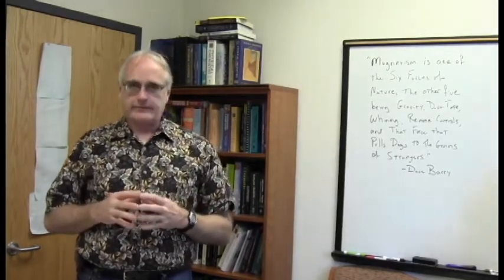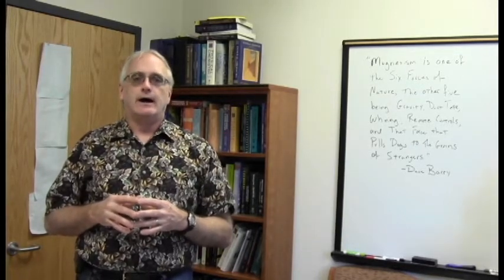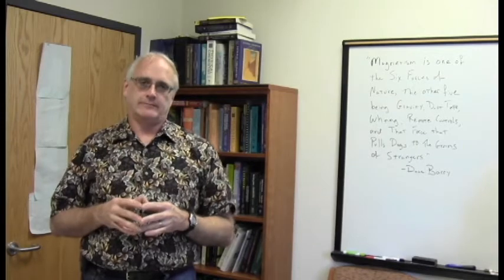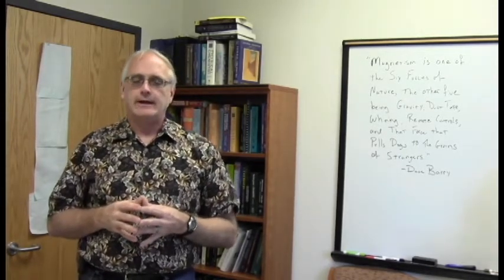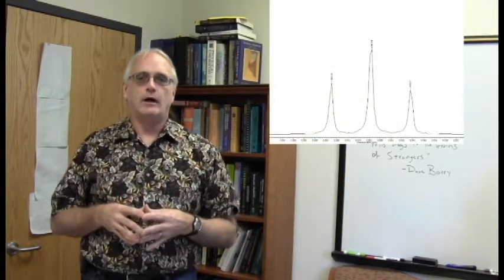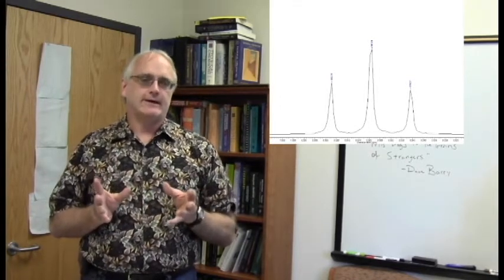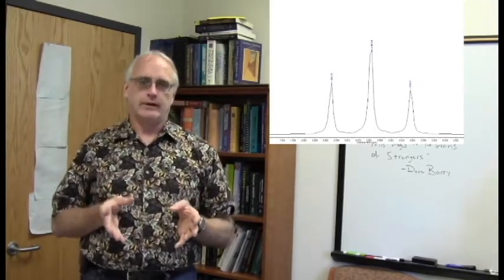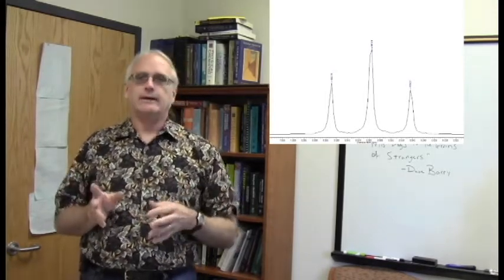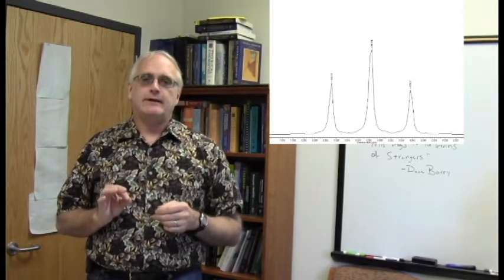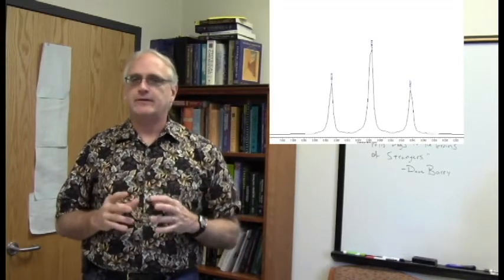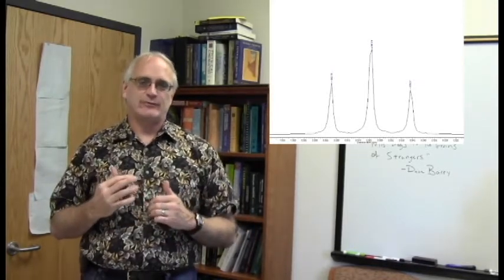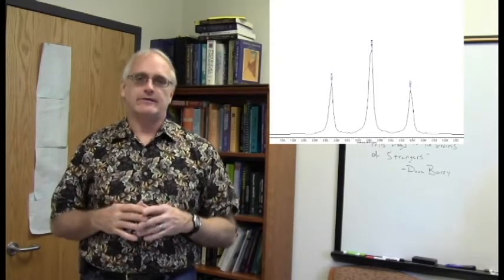Shimming is important because if we don't get this right — even with a little variation in the magnetic field from the top versus the bottom, or left versus right of the sample tube — it can have a drastic effect on our spectrum. For example, if the instrument was poorly shimmed, there might be a 10 hertz difference across the tube. That would mean protons throughout the tube each experience a slightly different magnetic field, changing their spin state energies. It takes a nice high-resolution triplet and turns it into something broad and unresolved.